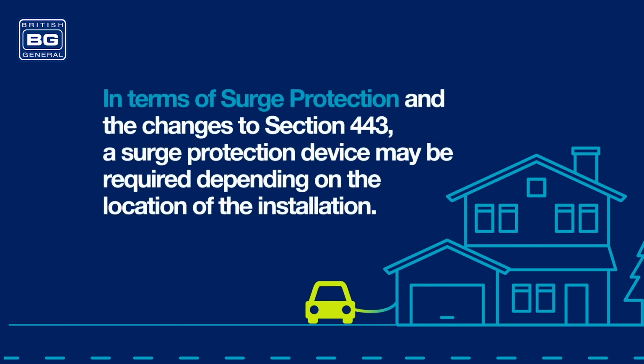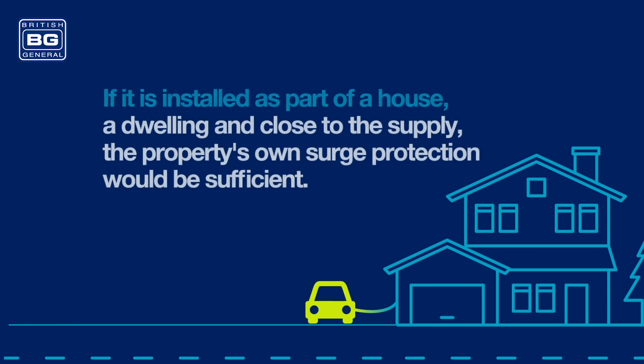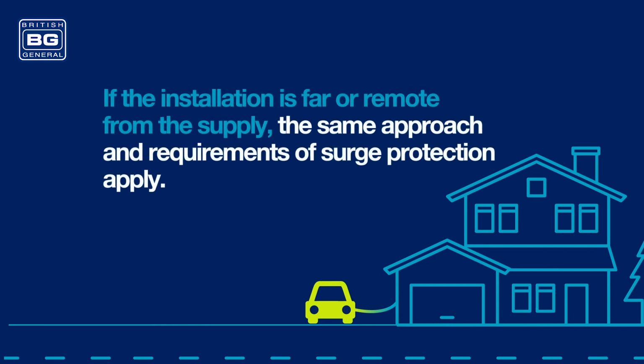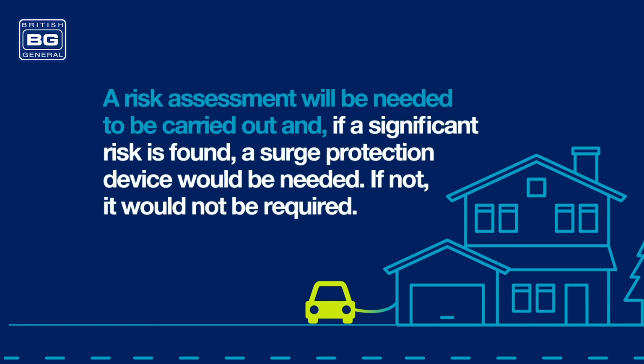In terms of surge protection and the changes to Section 443, a surge protection device may be required depending on the location of the installation. If it is installed as part of a house, a dwelling, and close to the supply, the property's own surge protection would be sufficient. If the installation is far or remote from the supply, the same approach and requirements of surge protection apply. A risk assessment will need to be carried out, and, if a significant risk is found, a surge protection device will be needed. If not, it would not be required.